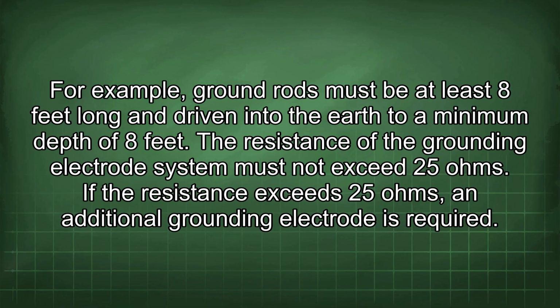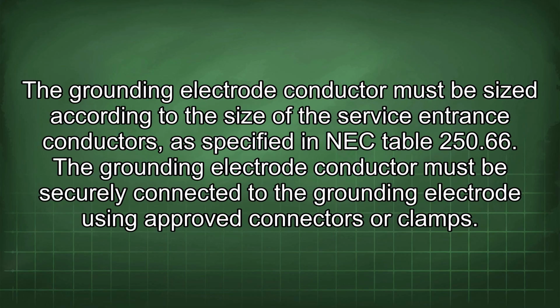For example, ground rods must be at least 8 feet long and driven into the earth to a minimum depth of 8 feet. The resistance of the grounding electrode system must not exceed 25 ohms. If the resistance exceeds 25 ohms, an additional grounding electrode is required. The grounding electrode conductor must be sized according to the size of the service entrance conductors, as specified in NEC Table 250.66. The grounding electrode conductor must be securely connected to the grounding electrode using approved connectors or clamps.